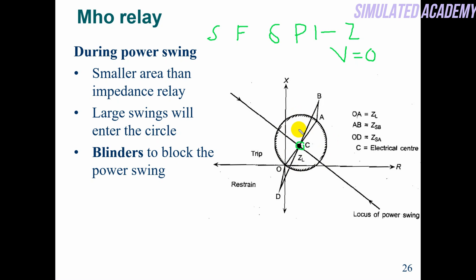So it is clear that there are chances the electrical center may come inside the circle, but this is also a limitation of this relay — the electrical center coming in between. For this, a blinder is used: either reduce the size of the relay circle or use a blinder.